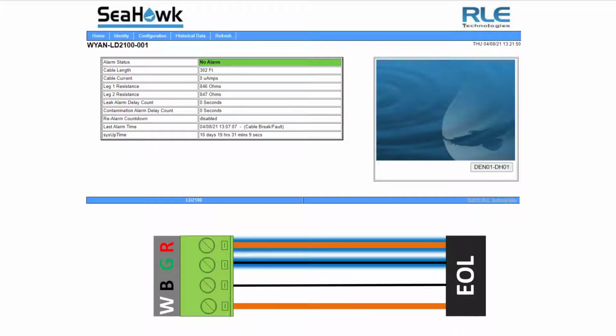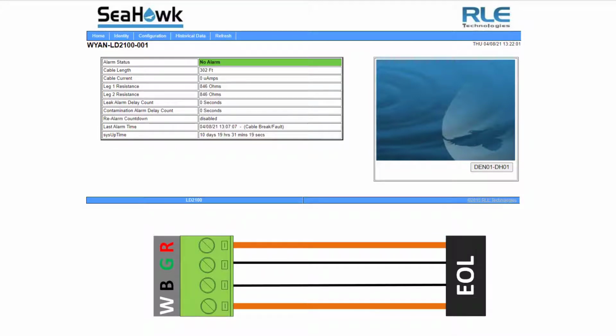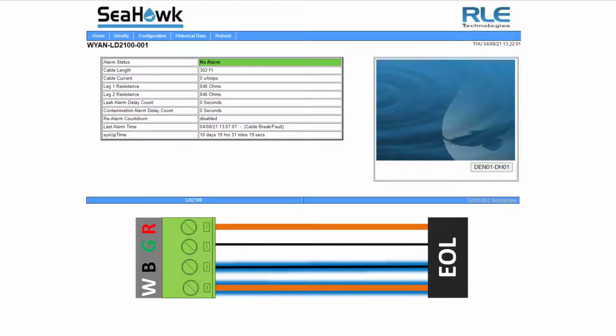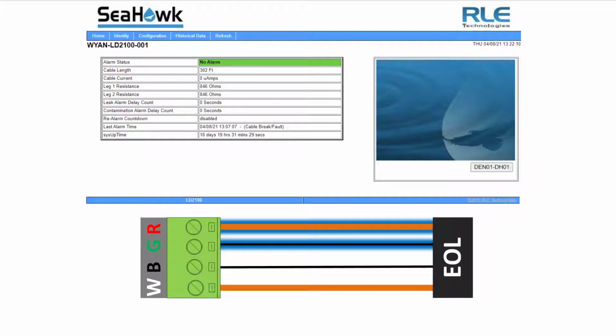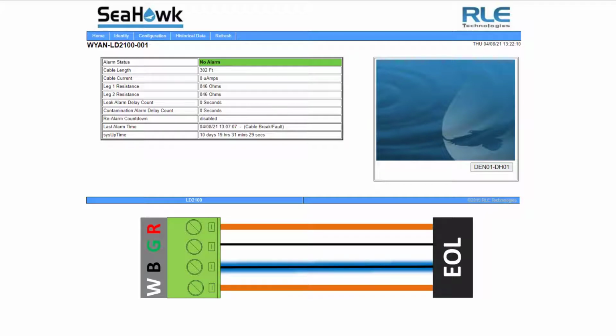So the system is constantly checking continuity and for leaks. It'll send a signal out on the white wire and look for a return signal on the black, which verifies leg 1. Then you have a signal being sent out on the red lead and a return coming in on the green lead, which checks the continuity on leg 2. Then it'll send a signal out on the black lead to see if any sort of microcurrent is returned on the green lead. That would give you the leak indication. So the system is constantly bouncing around between checking leg 1, leg 2, and leak, going through its basic operation.